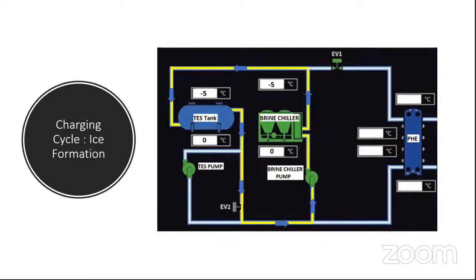See, for ice to form, the chiller has to be able to supply. We will also look at the chiller selection later on, in which you'll get to see that these chillers are actually dual mode chillers. This chiller can operate at the cooling temperatures of 5 degrees and 10 degrees, like we saw in the previous slide, and it can also deliver minus 5 degrees centigrade brine when it is working on a 5 degree delta T.